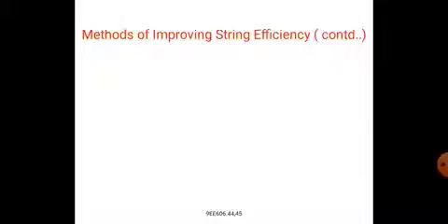The performance of a string depends on the value of M or K. If M is increased, the division of voltage becomes more equalized. When M is small, the top units perform very little work, and adding units has very little effect on the voltage across the unit adjacent to the line conductor. Therefore, for better performance, it is essential to equalize the potential across each insulator of a string.